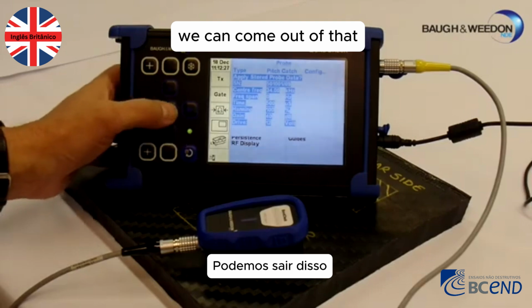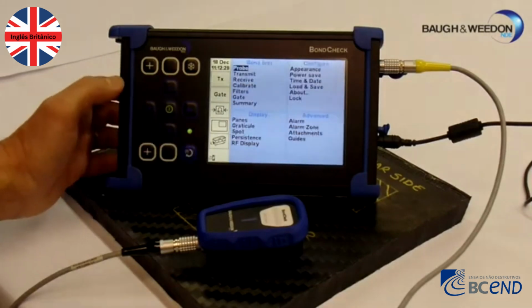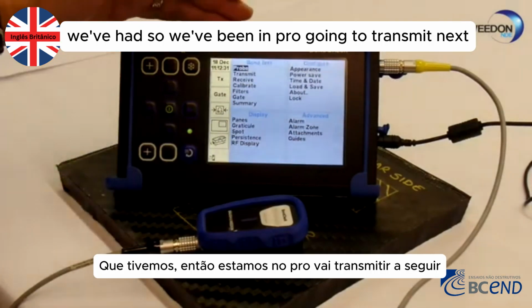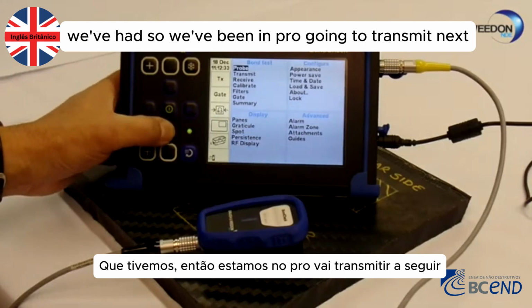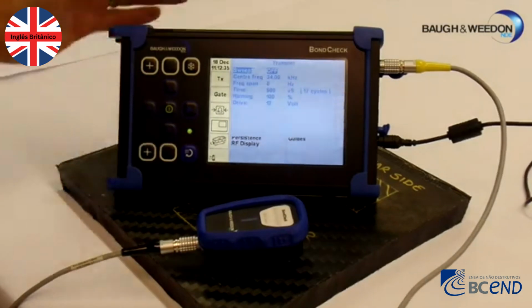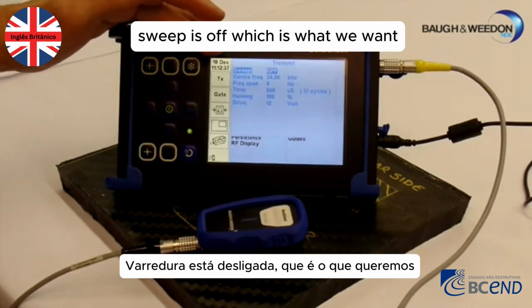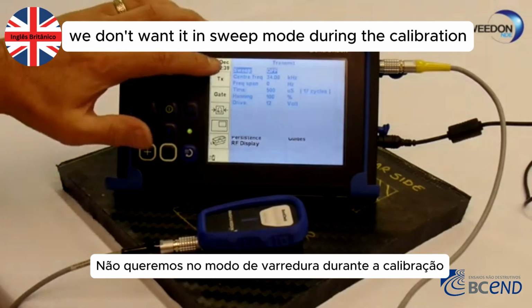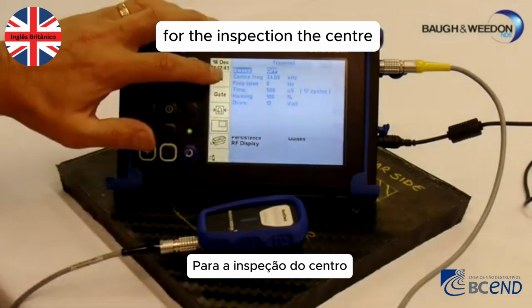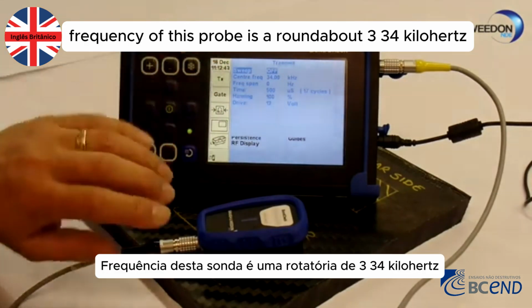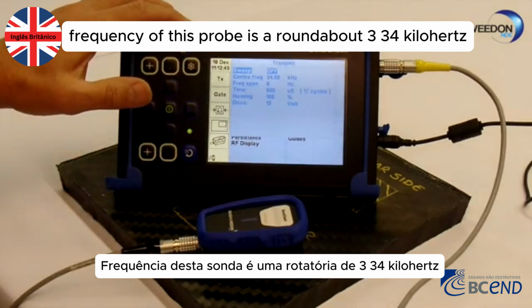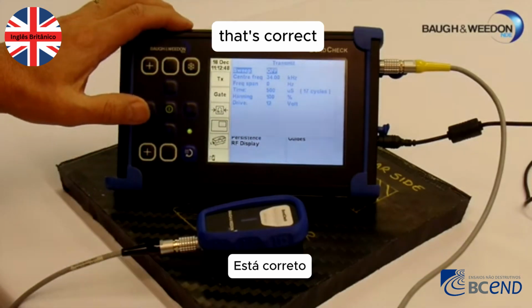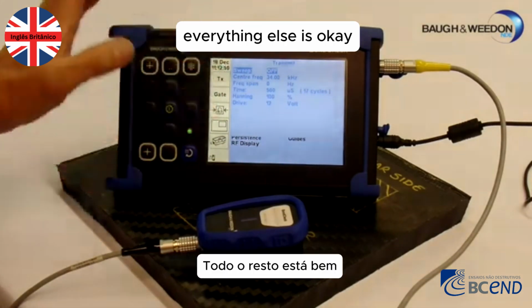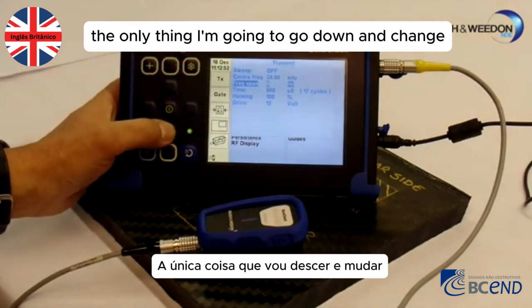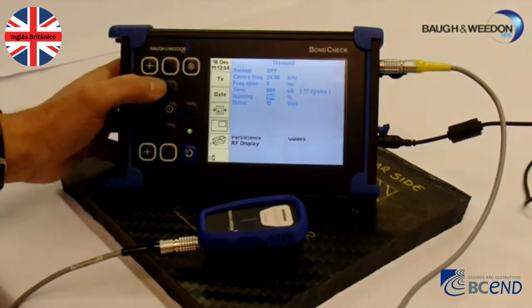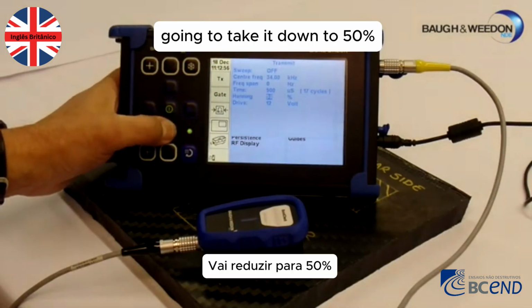We can come out of that. We've been in probe, we're going to transmit next. Sweep is off, which is what we want. We don't want it in sweep mode during the calibration for the inspection. The center frequency of this probe is around about 24 kilohertz, that's correct. Everything else is okay. The only thing I'm going to go down and change is the Hanning. I'm going to take it down to 50%.